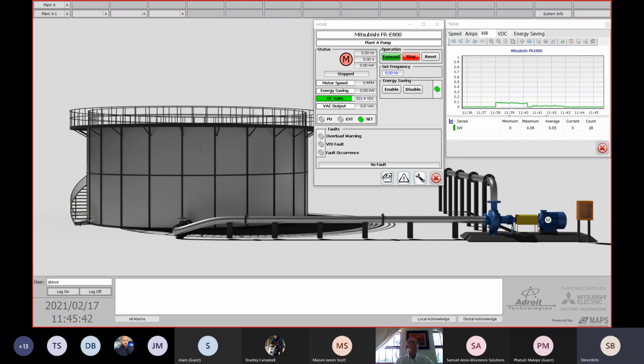Using our VFDs, we have a built-in active front end, so you will have a huge reduction in harmonics. But we also have an additional active front end that you can install to reduce harmonics even further if you still have that problem. But please note that the active front end will only filter out the harmonics generated by the drive, not by any other external equipment. Does that satisfy the question?